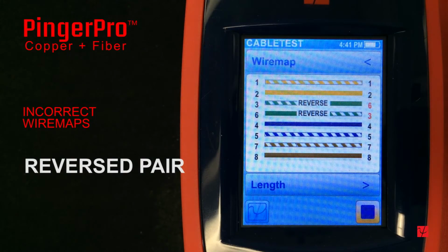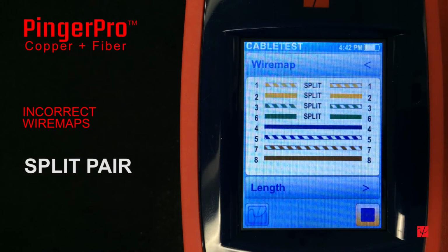A split pair is the most difficult WIREMAP problem to detect. It occurs when a pair is connected using wires of 2 different twisted pairs. One wire in each pair is reversed on both ends, which causes the signal to be sent on pairs that are not twisted together. Because the wires are not twisted, they do not cancel the EMI generated by the wires and have very high crosstalk. A device installed with a cable that has a split pair will usually connect and operate, but performance will be poor due to lost and corrupted packets caused by the high levels of crosstalk.